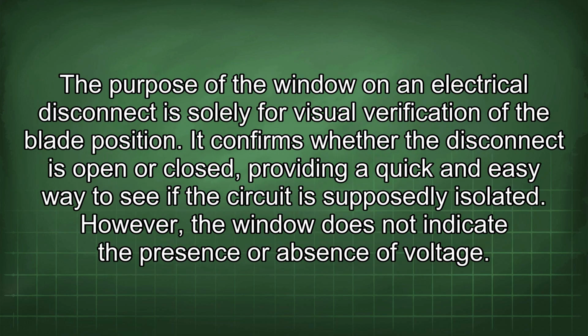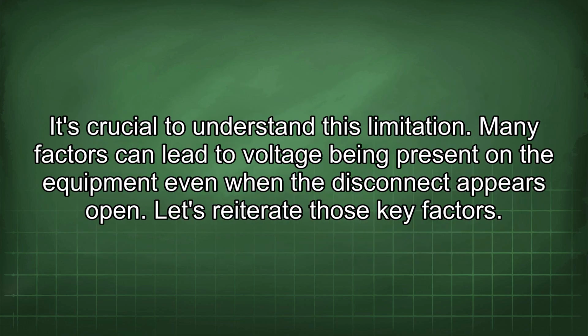The purpose of the window on an electrical disconnect is solely for visual verification of the blade position. It confirms whether the disconnect is open or closed, providing a quick and easy way to see if the circuit is supposedly isolated. However, the window does not indicate the presence or absence of voltage. It's crucial to understand this limitation. Many factors can lead to voltage being present in the equipment even when the disconnect appears open. Let's reiterate those key factors.